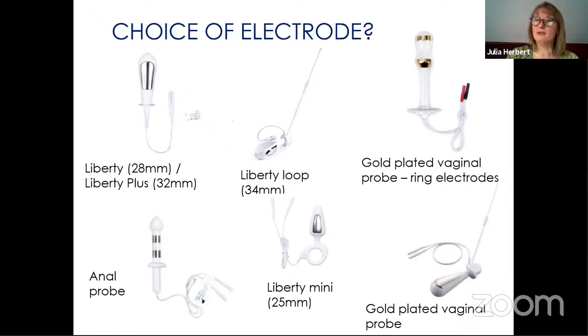And then you have an anal probe with the circular rings as well. That certainly would not be very easy for a patient to use at home because it's quite a long probe. They'd have to position it, whereas the Liberty Mini actually sits between the buttocks much better, and you can be a little bit more mobile with that one. And then we need to choose a program. So what parameters? Those in preset programs, somebody else has decided and put into the machine the frequency, the pulse duration, the duty cycle.